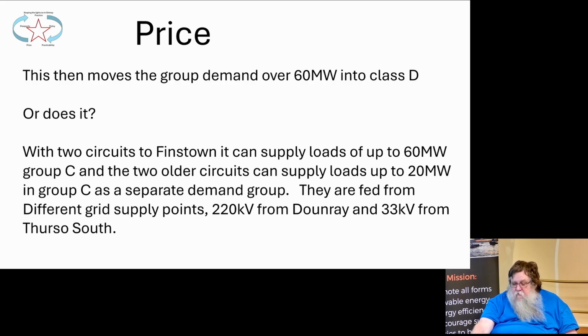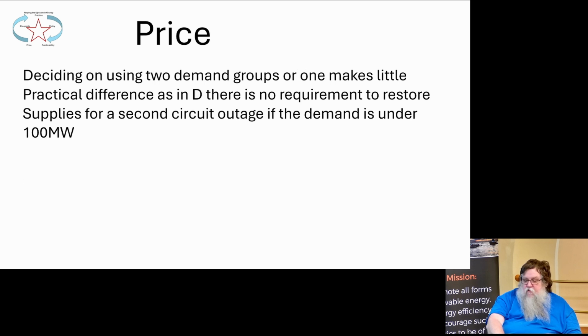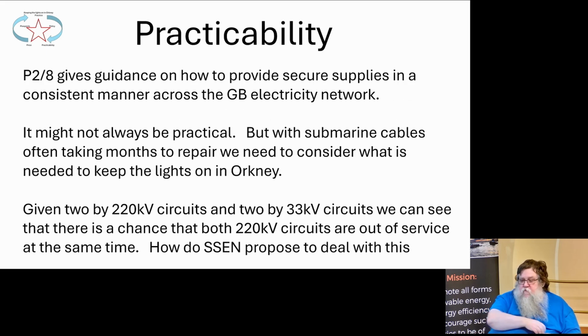It moves the group demand over 60 megawatts into Class D, and I've put "or does it", because actually, with 2 circuits to Finstown, you could supply 60 megawatts from Finstown, and the 2 older circuits can supply up to 20 megawatts. They're fed from different grid supply points. The 220 kVs coming from Dounreay and the 33 kV from Thurso South don't really make a lot of difference. So that's that slide.